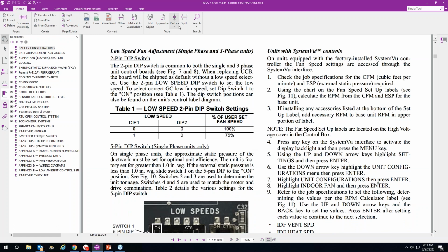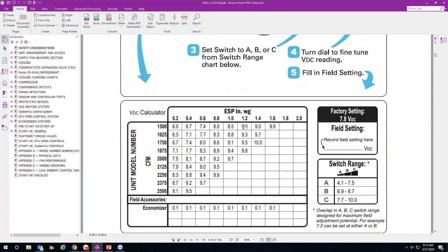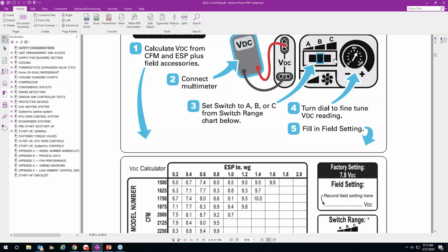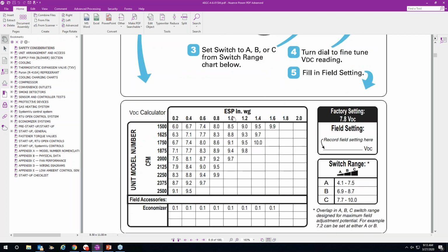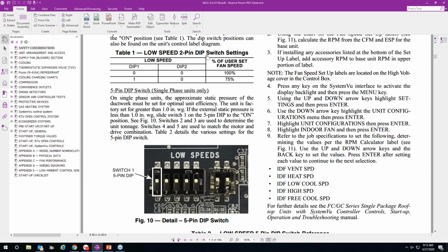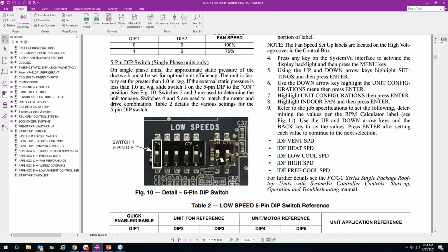All that I talked about on low speed fan setting, as far as the 2-pin dip switch, which would be for the 3-phase, here's your table right here. If dip switch 1 and 2 are both off, you get 100% of the user set fan speed. And again, the user set fan speed is where you set the ABC and the potentiometer, based off of, as you recall, your CFM requirement and your measured external static pressure. So when you go down here, low speed 2-pin settings: 100%, dip switch 1's off, 2's off. You want 75% of that, 1's on, and 2 is off. And then the 5-pin, all that information is right here.